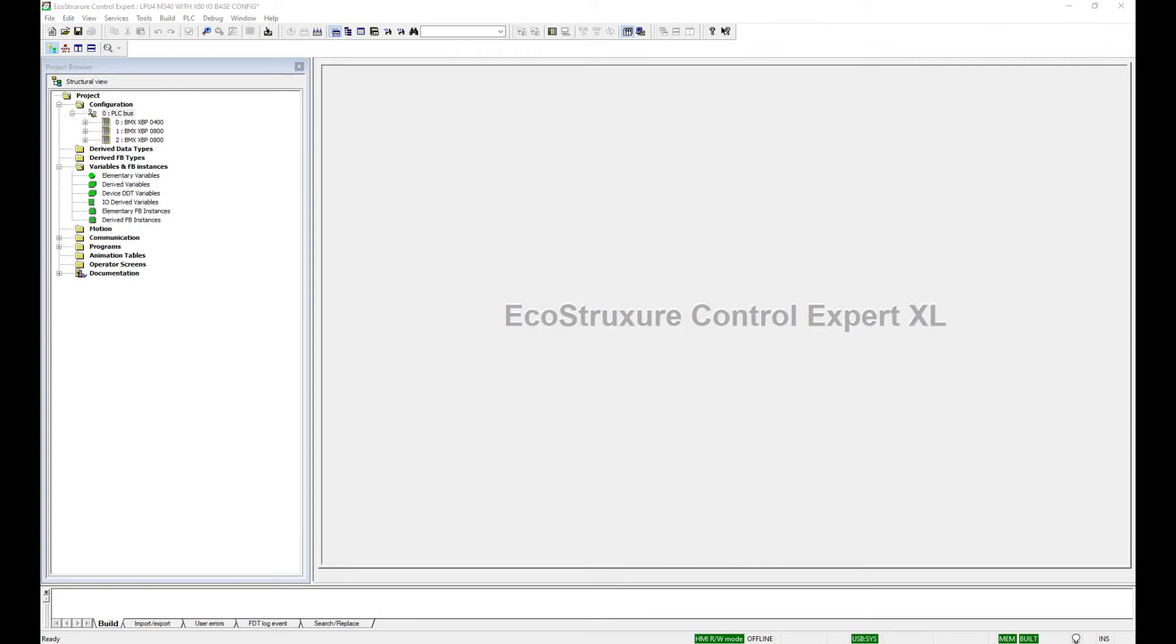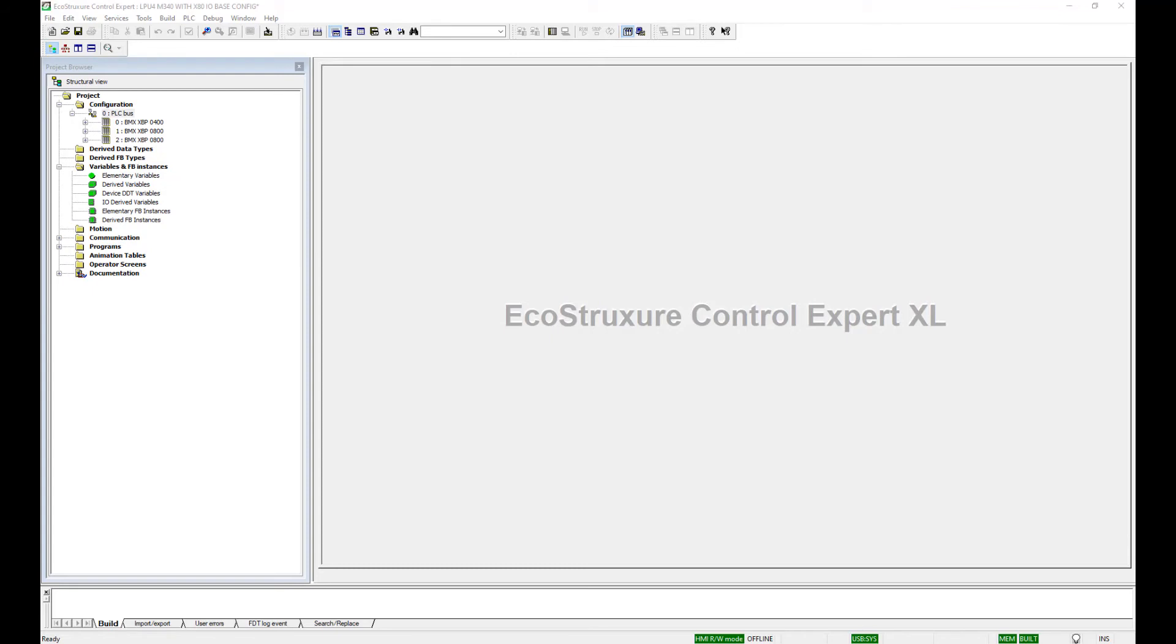The final step is to create a new Control Expert program with an M340 processor, a NOE module, and the correct X80 I/O modules for replacing the Quantum I/O modules. Rather than use an M340 with Ethernet, I chose the BMX P34-2000 with a NOE module because the NOE provides I/O scanning, NTP, as well as other capabilities not provided on the BMX P34-2020.